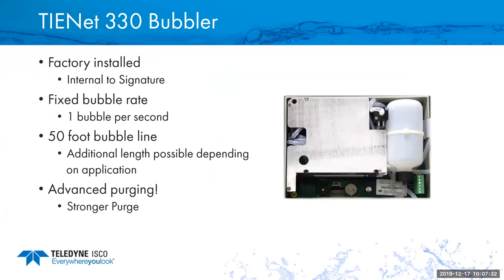The 330 bubbler is factory installed inside of the signature meter. You can get a 50-foot bubble line. It's got some purges that are larger purges to help clear the lines out so you don't have plugging as often. And they're done at just settable intervals that you can set in there as well to purge out the line to clean it out.